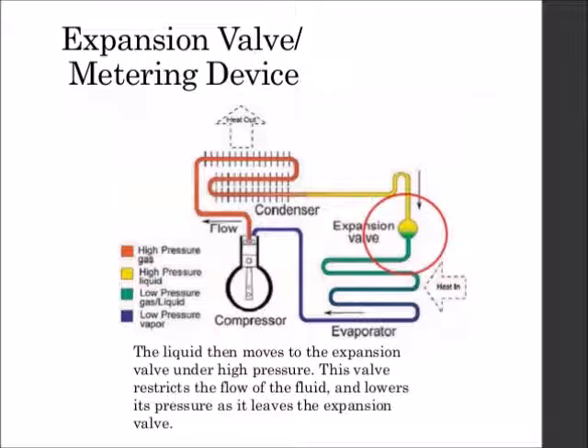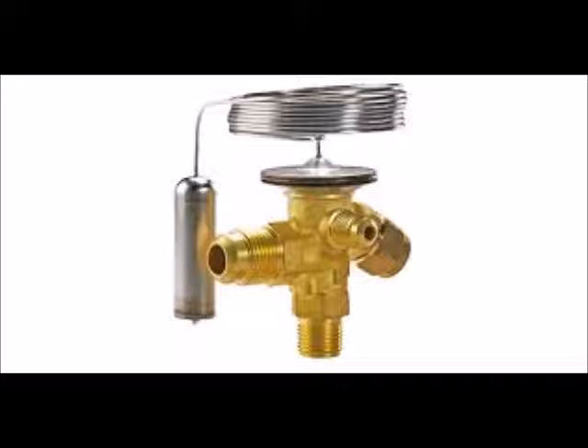In order for the higher-temperature fluid to cool, the flow must be limited into the evaporator to keep the pressure low and allow expansion back into the gas phase. The TXV has sensing bulbs connected to the suction line of the refrigerant piping. The gas pressure in the sensing bulbs provides the force to open the TXV, therefore adjusting the flow of refrigerant and the superheat. Expansion valves are flow-restricting devices that cause a pressure drop of the working fluid. The valve needle remains open during steady-state operation, and the size of the opening is related to the pressure and temperature of the evaporator.